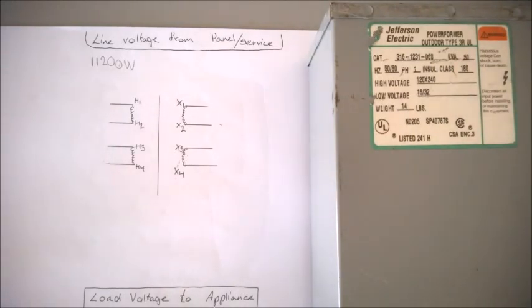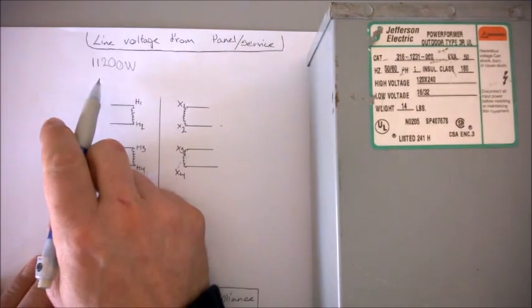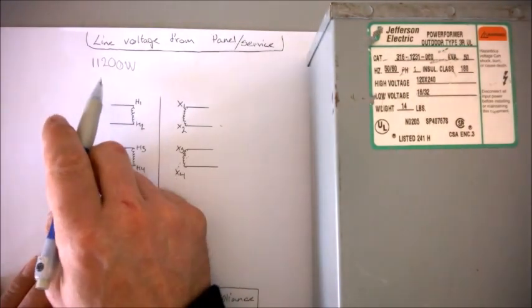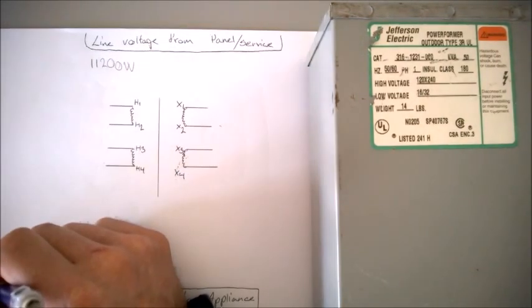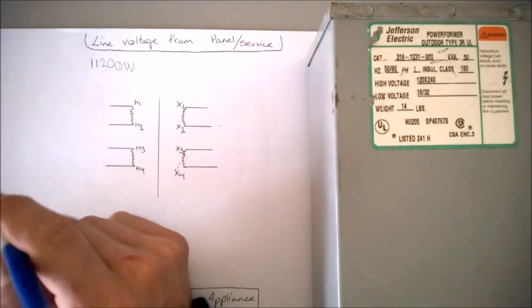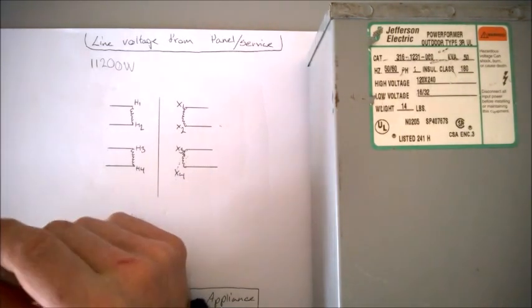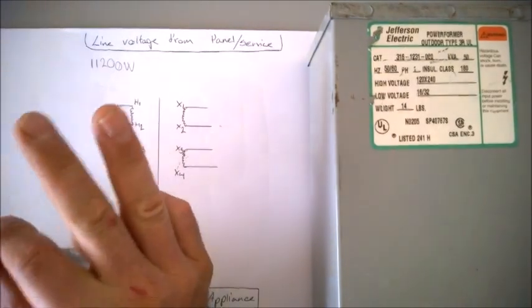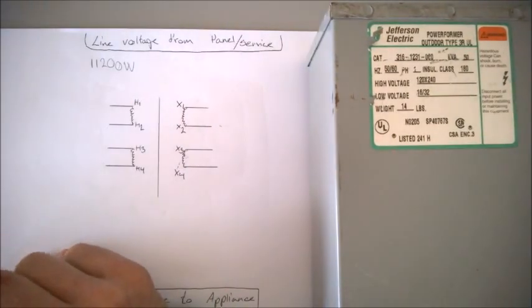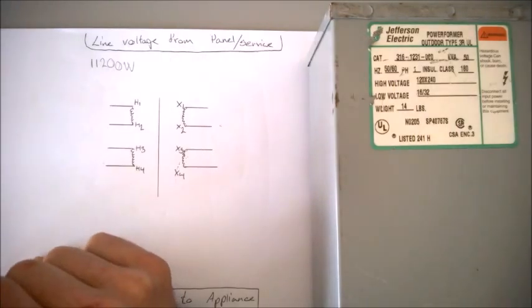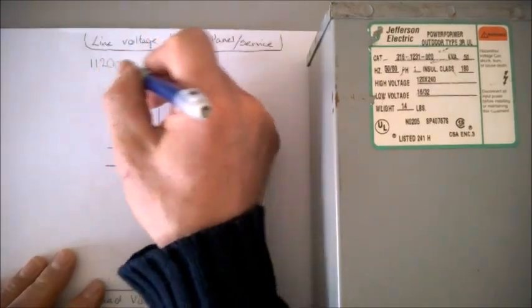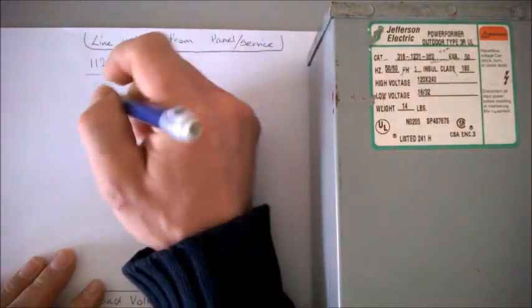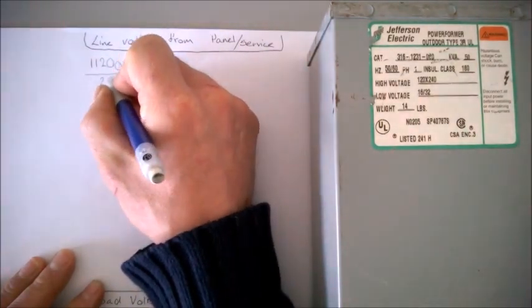Our machine's ETL listing says 11,200 watts—that's what it's consuming total. Let's say it's a single-phase load, that means it needs two poles from the service, meaning it's a two-pole breaker in our panel. So for us to dissect the 11,200 watts, we're going to have to divide it by this magic number here.